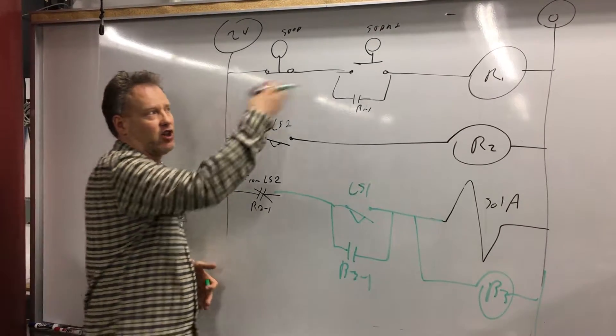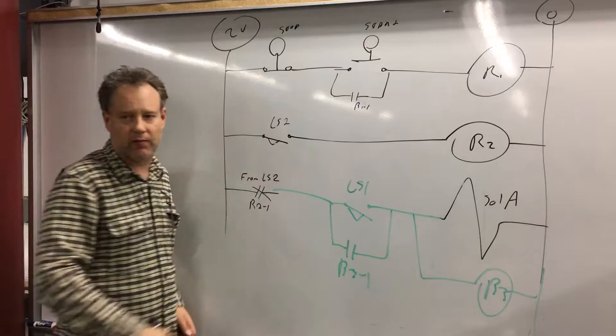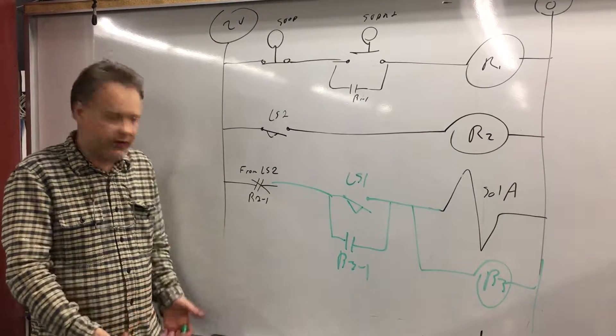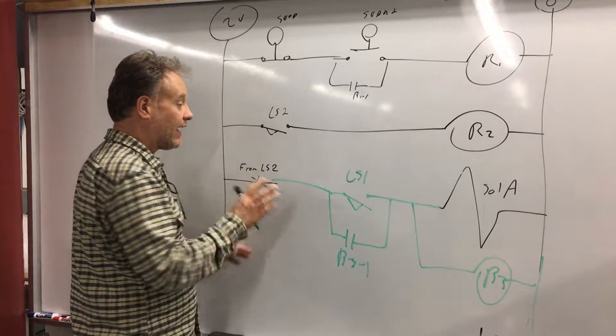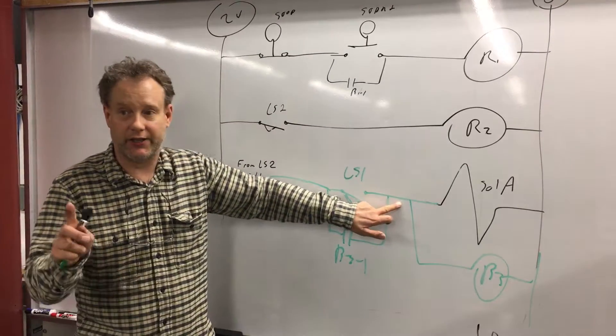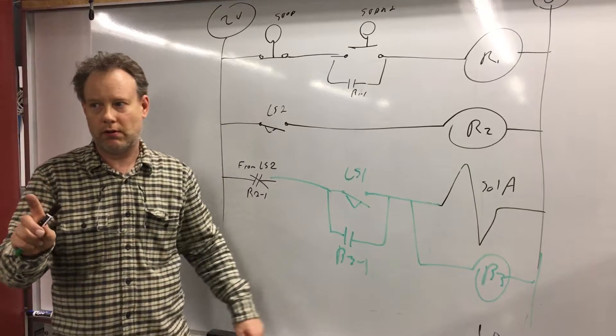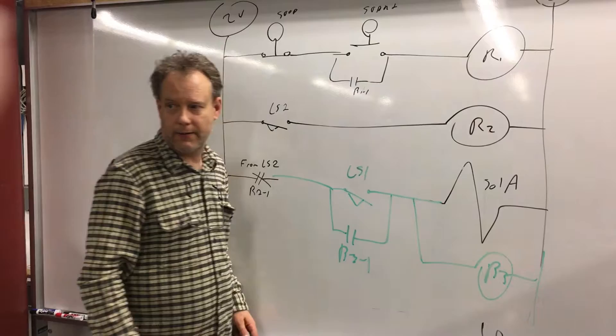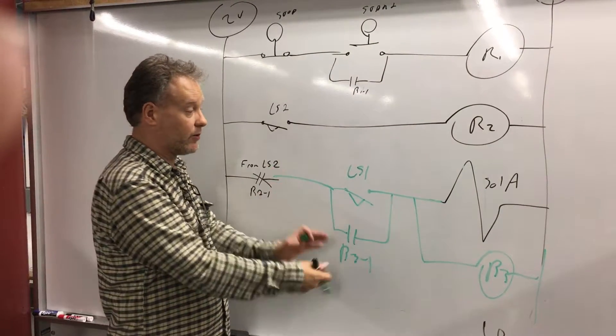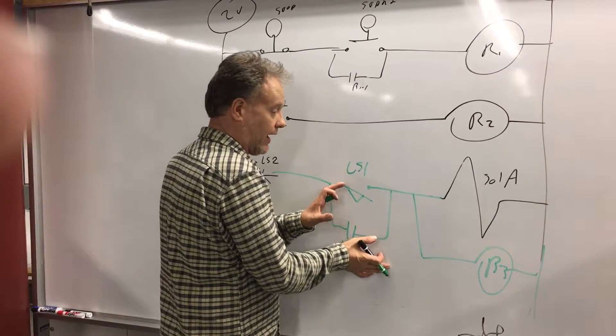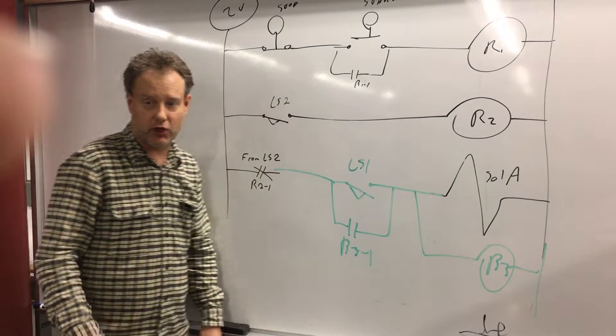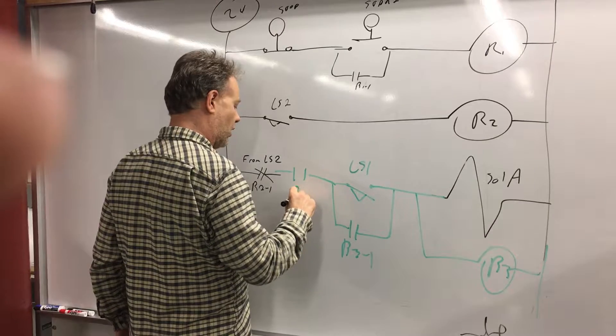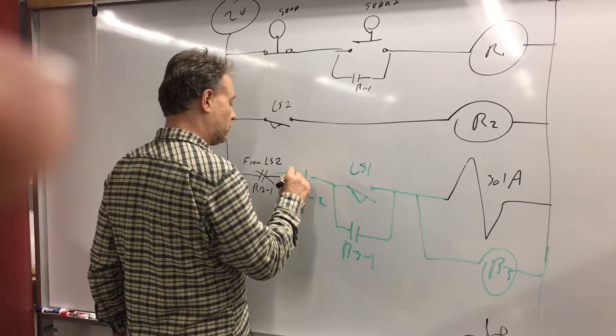So how do I add the logic of the start button in here somewhere? I can either put it there or there. We don't put anything in between our holding circuit and the actual relay itself. In this case I'm going to put it right here — R1-2.